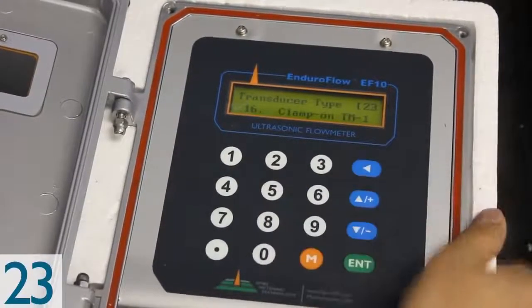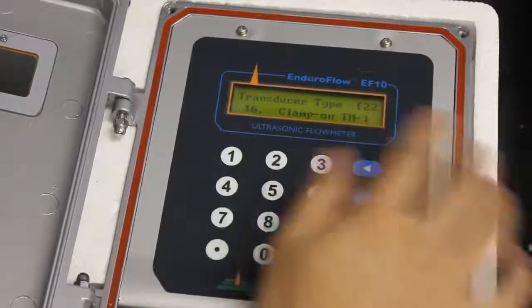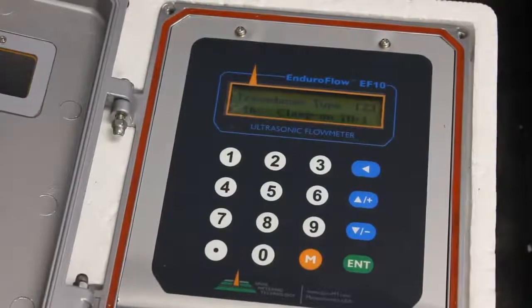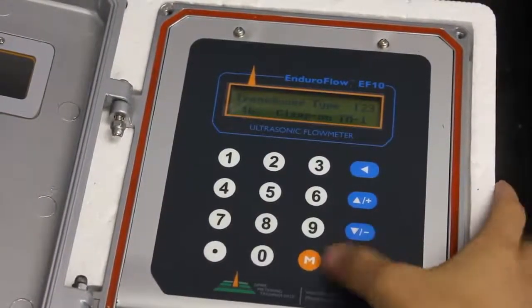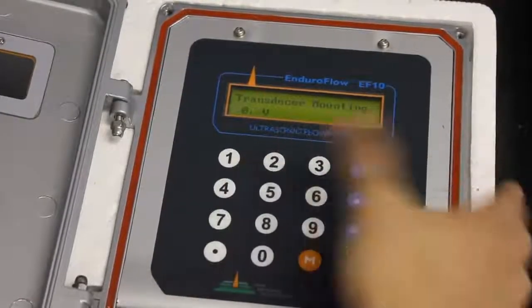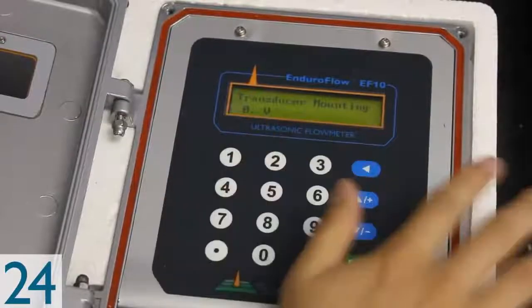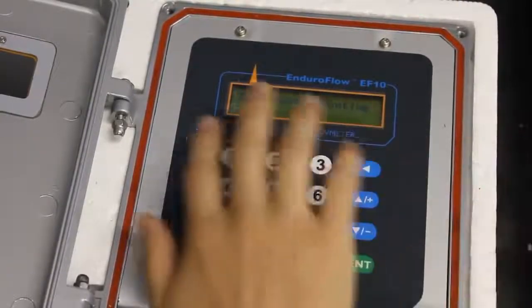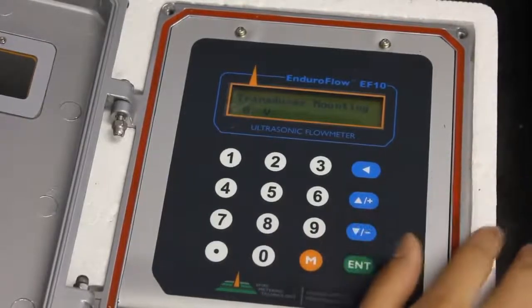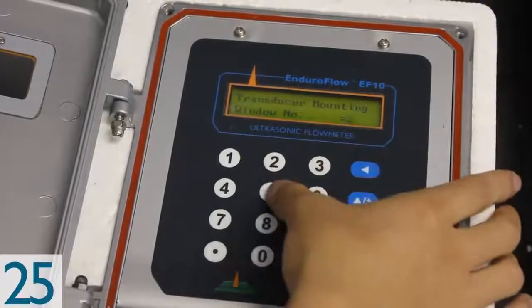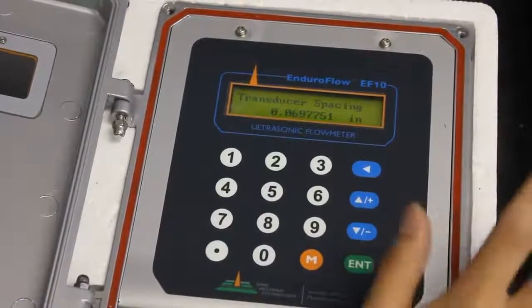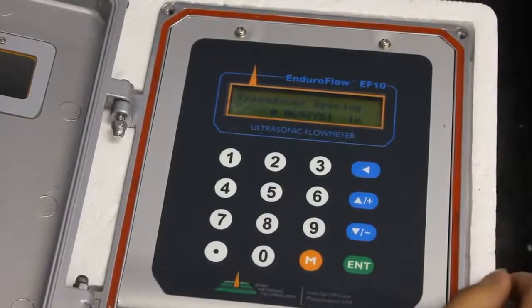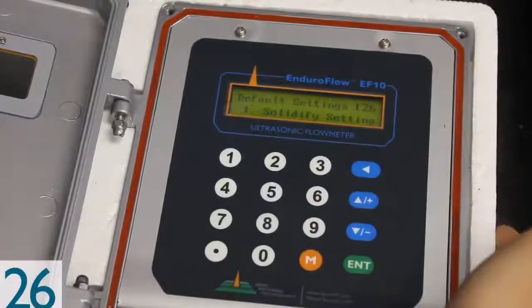Next we go to menu 23 to set your transducer type. We're going to be using the clamp on TM1s today. Right here. And then next you go to menu 24 to set your mounting method. Talk more about this later, but generally you would just use V method. You could also use Z method but that's for much bigger pipes, maybe if it had a 10 inch diameter or something like that. Then go to menu 25. This tells you how far apart your transducers are supposed to be. But a lot of times you end up having to adjust the transducers. We'll talk more about that later too.